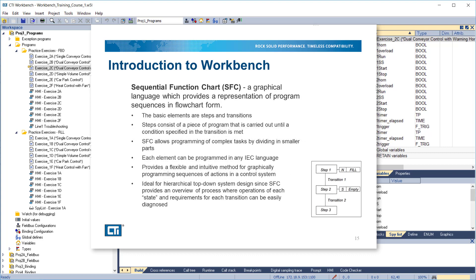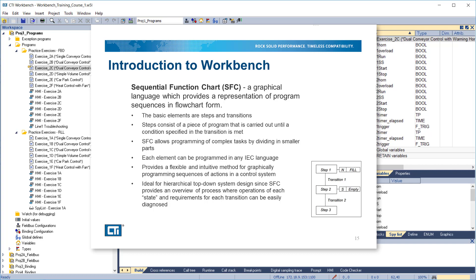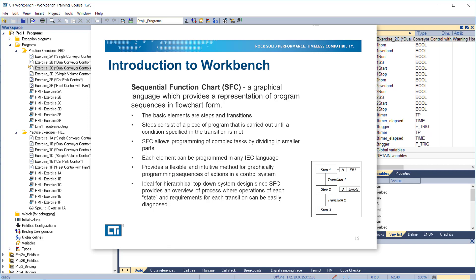Sequential function chart is a graphical language which provides a representation of program sequences in flowchart form. The basic elements of SFC are steps and transitions. Steps consist of a piece of program that is carried out until the condition specified in the transition is met. SFC allows programming of complex tasks by dividing them into smaller parts, with each element programmable in any IEC language. It provides a flexible and intuitive method for graphically programming sequences of actions and is ideal for hierarchical top-down system design, since SFC provides an overview of the process where operations of each state and requirements for each transition can be easily diagnosed.